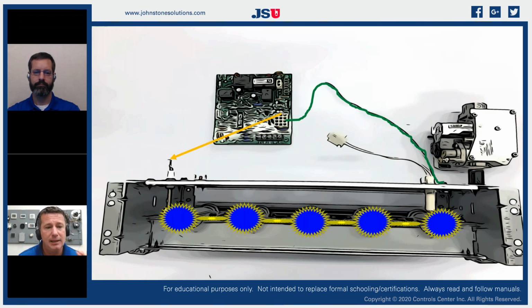So we apply electrons into the flame. As those electrons are passing through that flame to ground, they get chopped up. The AC sine wave gets chopped up and it looks like a DC voltage now. It doesn't look like an AC voltage. The clean sine wave is gone and it's been chopped up. So we create a DC current that is passing through that flame. And because we have applied a load onto those carbon molecules, we actually have current passing through there. So we now create a load in amps on DC voltage, and we read it as microamps DC. But it is absolutely applied AC voltage.